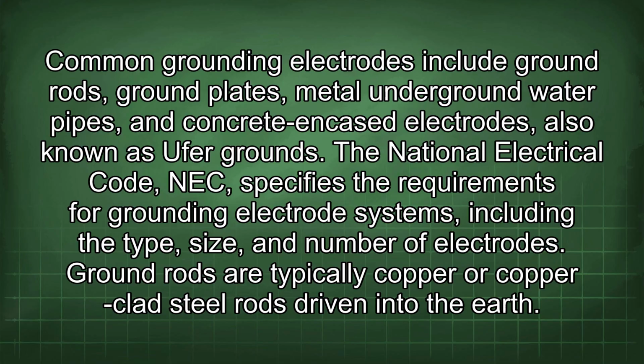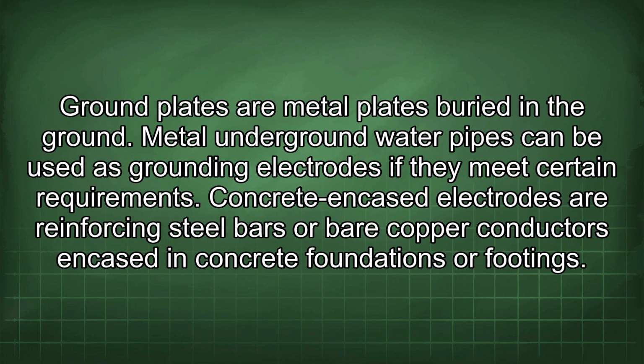Ground rods are typically copper or copper-clad steel rods driven into the earth. Ground plates are metal plates buried in the ground. Metal underground water pipes can be used as grounding electrodes if they meet certain requirements. Concrete-encased electrodes are reinforcing steel bars or bare copper conductors encased in concrete foundations or footings.